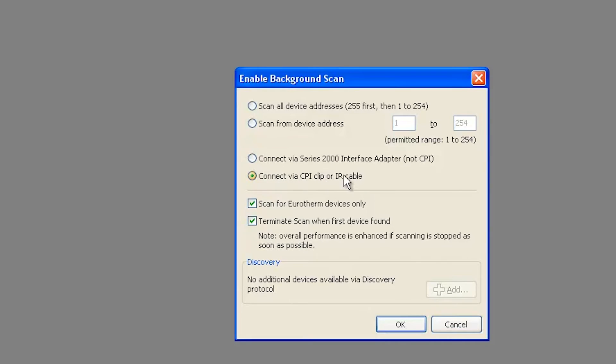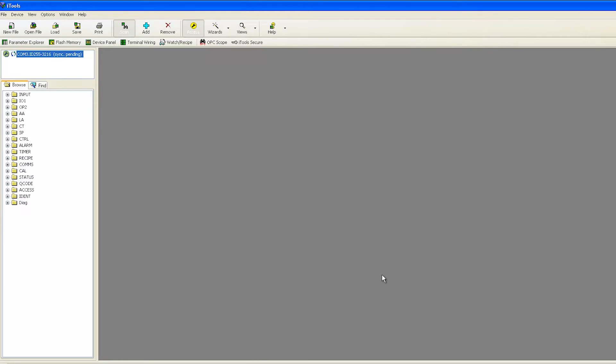Select Connect via CPI Clip or IR Cable and press OK. You can also select Scan all device addresses since controllers connected to the CPI clip will be found at address 255 regardless of the address configured in the controller.